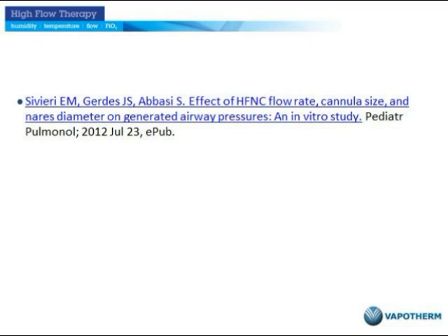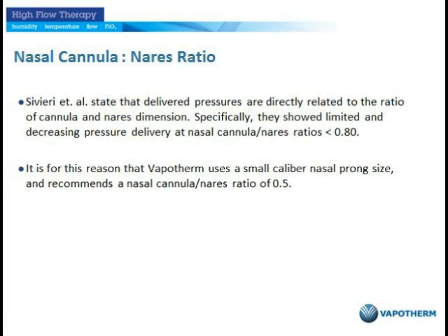Here's the reference for some of the relationships between flow rates, cannula size, and nares diameters on airway pressures which are generated. It's an in vitro study published by Sivieri and colleagues in Pediatric Pulmonology in July of last year. They state in their study that the delivered pressures are directly related to the ratio of cannula and nares dimension. That's actually one of the most, if not the most, important variable.